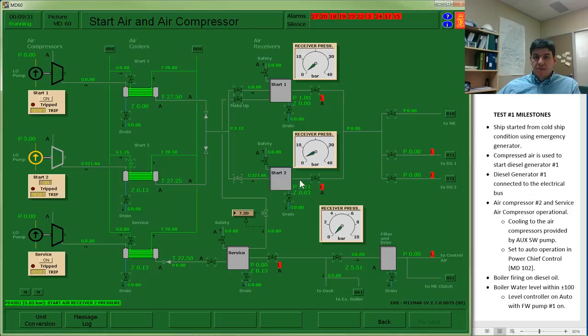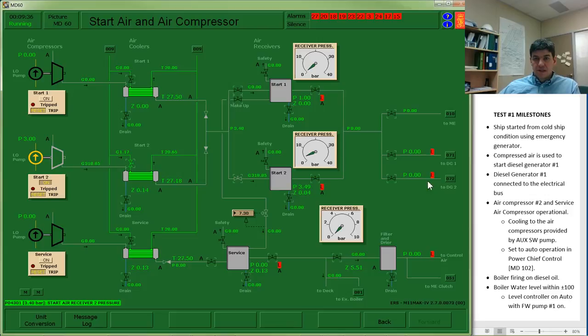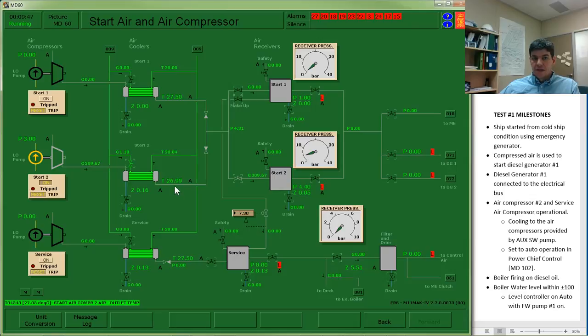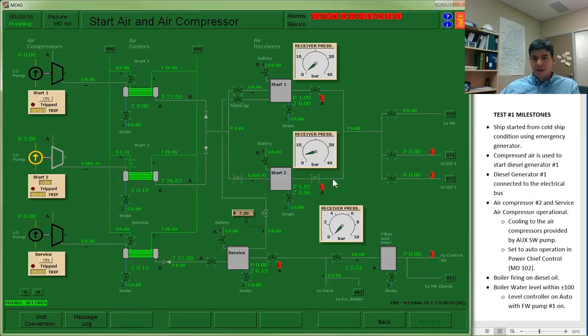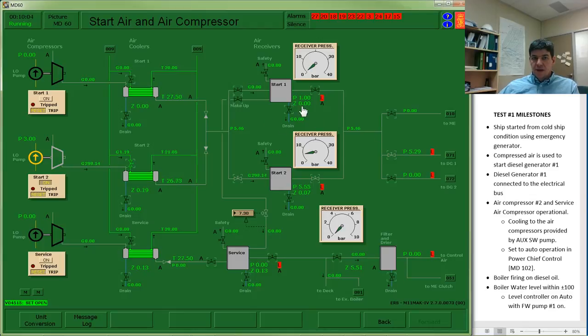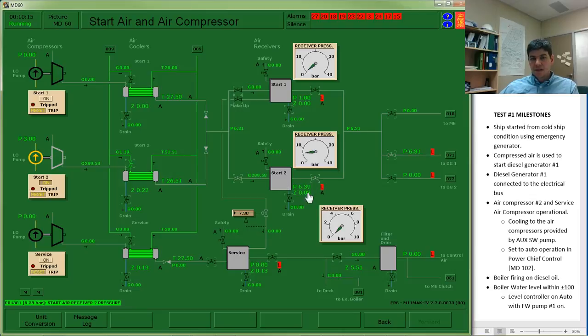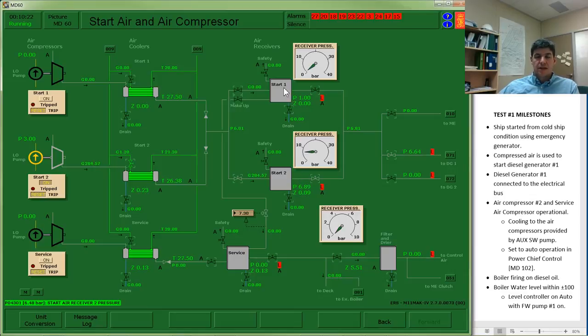I'll need at least 15 bar of pressure in order to get my diesel generator started. Before I leave this page, because at this point I could go and start working at my diesel generator number 1, what I want to do is ensure first of all that my temperature is under control, and it looks like it's not rising. It's actually quite low, so that's good. The cooling water is doing its job. I'll open up pathways to my diesel generator 1. Before I leave the page, I just want to make sure I haven't opened up any drains that are causing me to lose any air. And generally I want to only fill up one tank at this point so that it doesn't take twice as long.